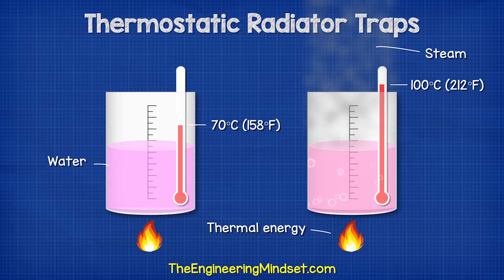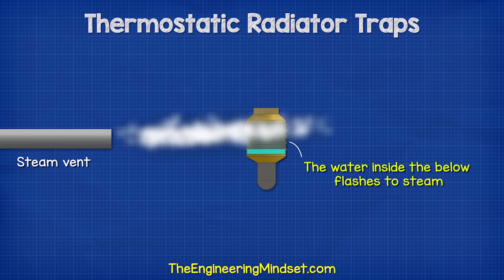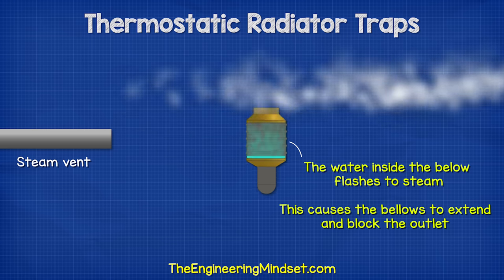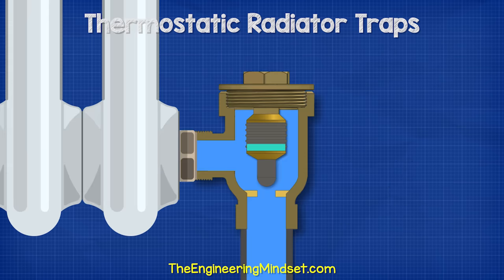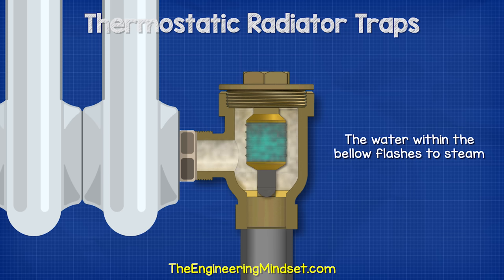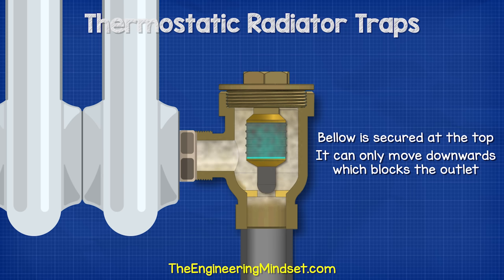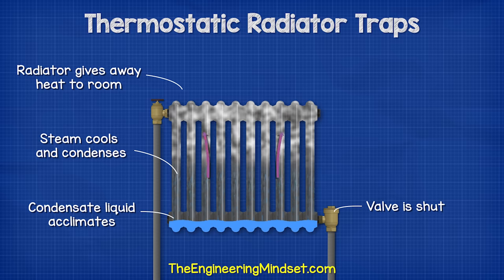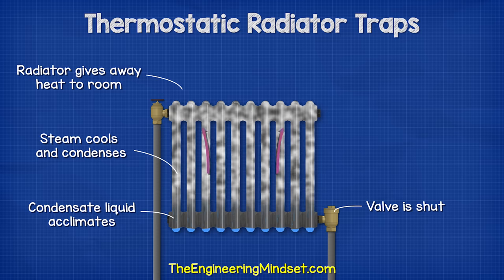Steam exists above 100°C (212°F), which is above the boiling point of water. When steam comes into contact with the bellow, the water inside is heated and flashes into steam almost instantly, causing a rapid increase in volume that forces the bellows to extend, blocking the outlet of the valve. On system startup the bellow is open and the trap is full of condensate. As steam enters the trap it heats the bellow, the water inside flashes to steam, pressure inside the bellow increases, and since the bellow is secured at the top it can only extend downward — plugging the outlet and stopping steam from flowing into the condensate line. This gives the steam in the radiator a chance to give away its heat to the room, then cool down and condense into a liquid.